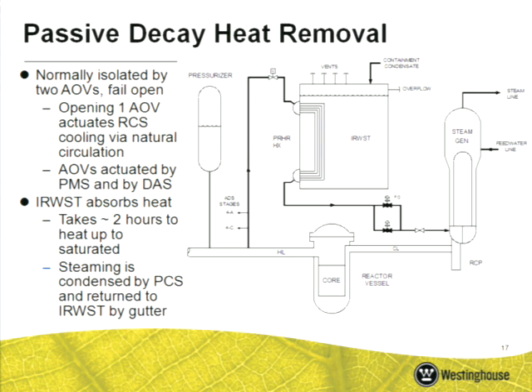And after a while, after a couple hours, actually, the big tank of water, 500,000 gallons, the water starts to boil, and the steam comes out this vented tank, and we'll talk about what happens to the steam. We condense it on the containment and return it to the tank. So that after we actuate, just after we open these valves, then without operator action or without anything, the core cooling remains going really forever. I mean, there's nothing that would stop this process, as long as you keep returning some inventory of water to this tank so that it can cool the core.